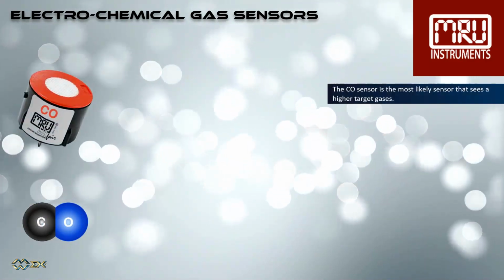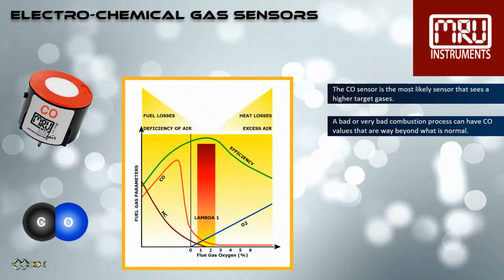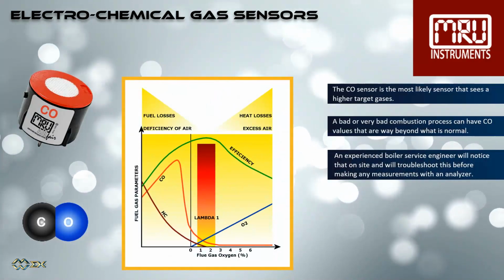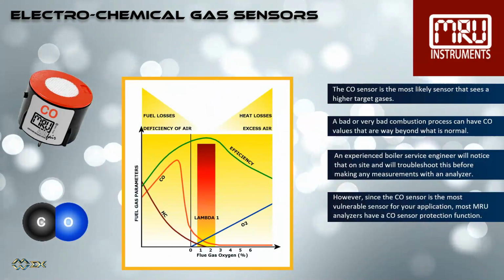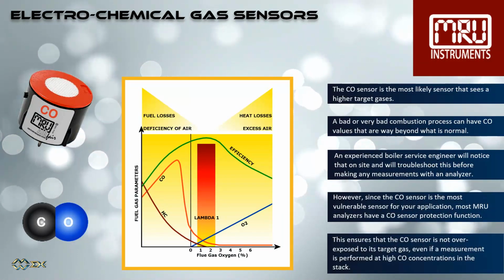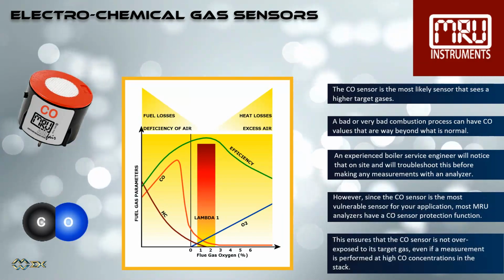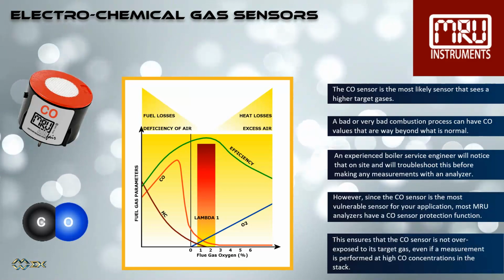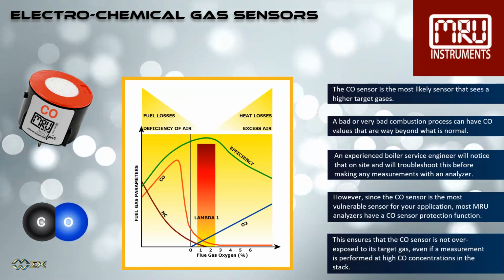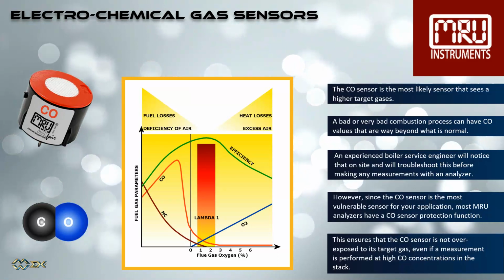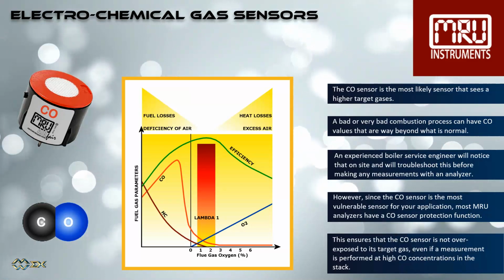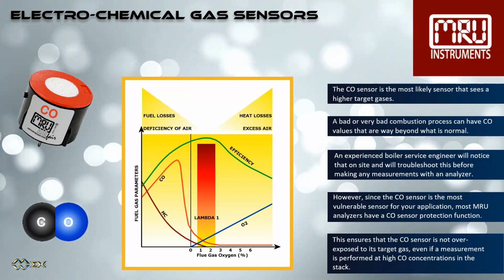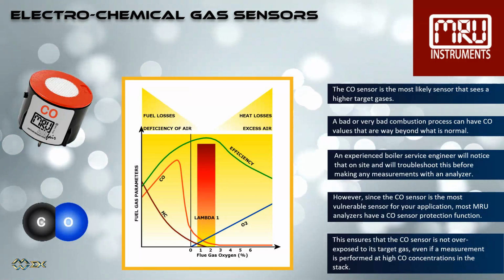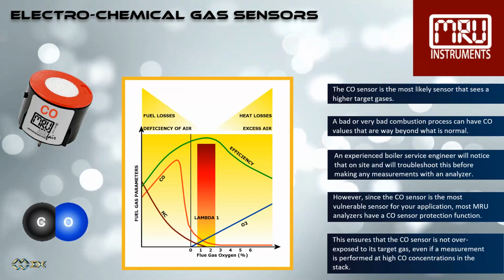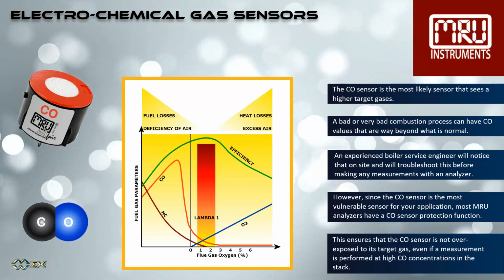The CO sensor is the most likely sensor that sees higher target gases. A bad or very bad combustion process can have CO values that are way beyond what is normal. An experienced boiler service engineer will notice that on site and will troubleshoot this before making any measurements with an analyzer. However, since the CO sensor is the most vulnerable sensor for your application, most MRU analyzers have a CO sensor protection function. This ensures that the CO sensor is not overexposed to its target gas, even if a measurement is performed at high CO concentrations in the stack.